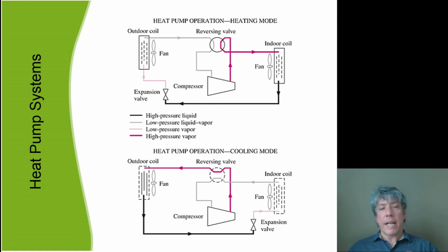So then you see that black arrow coming over horizontally at the bottom of the screen, and remember, it's a high temperature, high pressure liquid. Then it goes through an expansion valve, and that expansion valve allows the pressure to simply drop. So there's a transformation between the thermal energy, or the temperature, and the flow energy. Some of the fluid boils off, and the temperature drops drastically. So coming out of the expansion valve is a very low temperature and low pressure refrigerant.